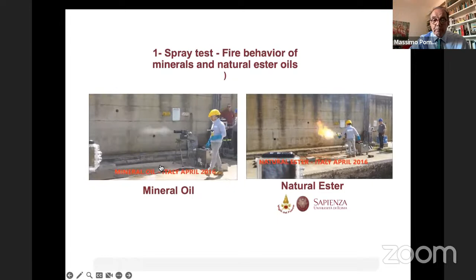Okay. Also, we simulated another test, on a distribution transformer. If you look carefully, there are two transformers. Both are green because we want identical transformers. We filled one transformer with mineral oil and the other with natural ester. So we were simulating what happens under an electrical breakdown, an electrical arc, in both cases.